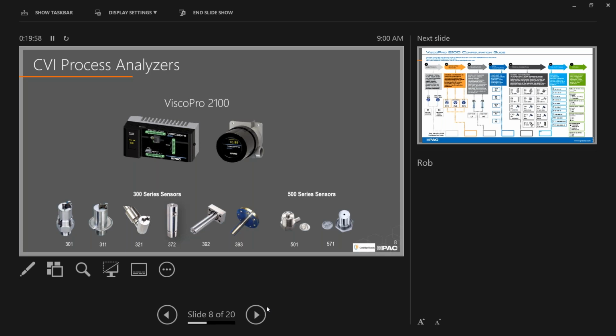So we have 6 300 series sensors on the left and 2 500 series sensors. The 300 series sensors, the diameters of the shaft are all the same, which is 30 millimeters. So really the difference of these sensors is how you would mount them in a process. So the 301 has a 1.25 inch NPT threaded connection. The 311, which is commonly used in inks and paints, has a quick release clamp with a 2-inch sanitary flange.